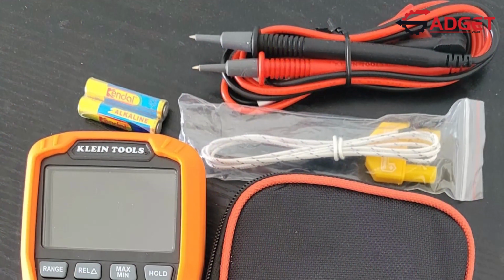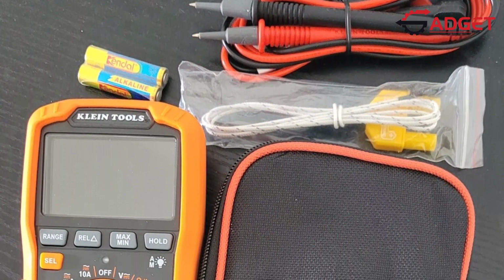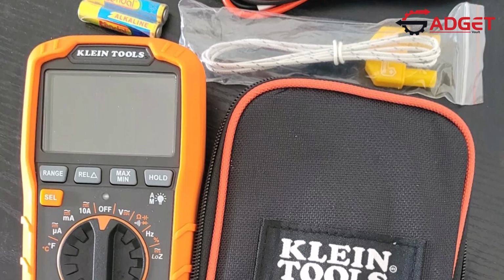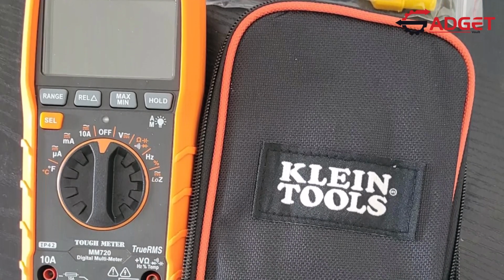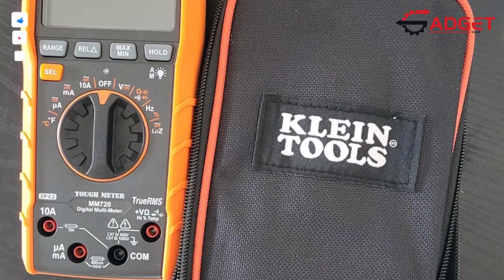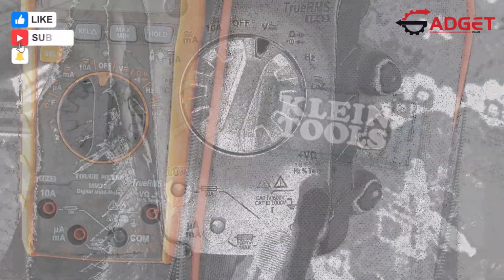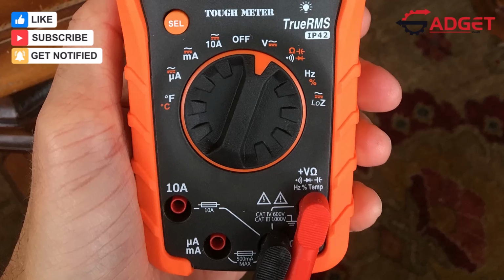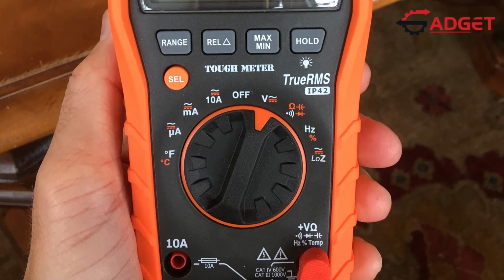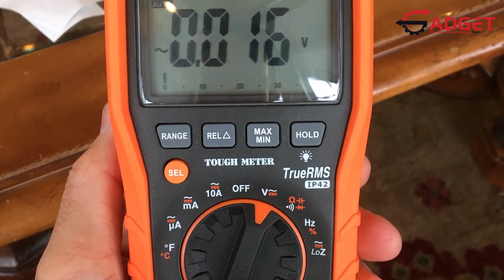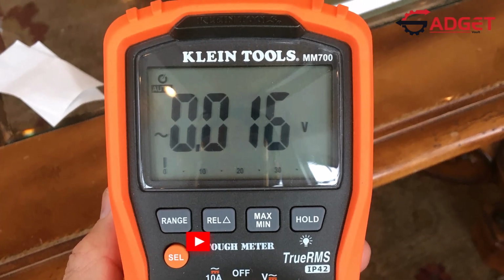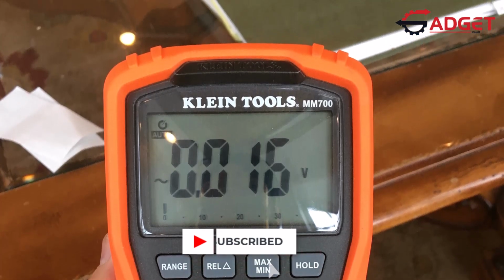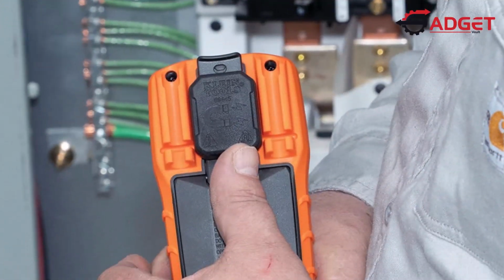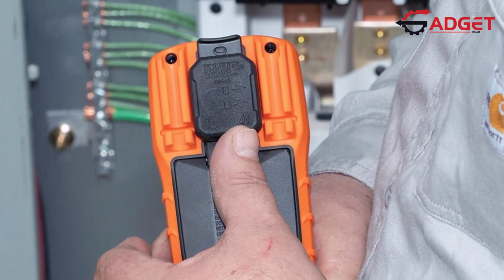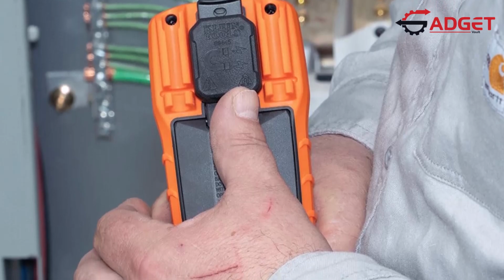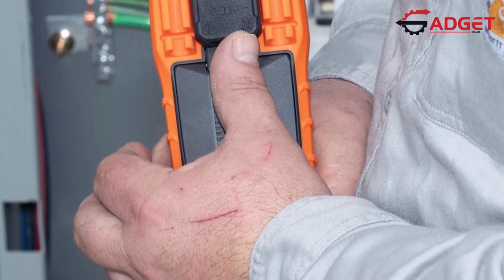What sets this multimeter apart is its additional functions like continuity, temperature, capacitance, frequency/duty cycle, diode testing, and a low-impedance low-Z mode. The low-Z mode is especially useful for detecting and eliminating ghost or stray voltages, ensuring that readings are both accurate and trustworthy. The auto-ranging with true RMS technology guarantees precise results even in non-linear load environments, making it suitable for residential, automotive, and industrial use.